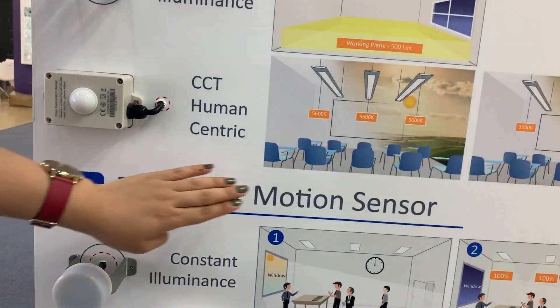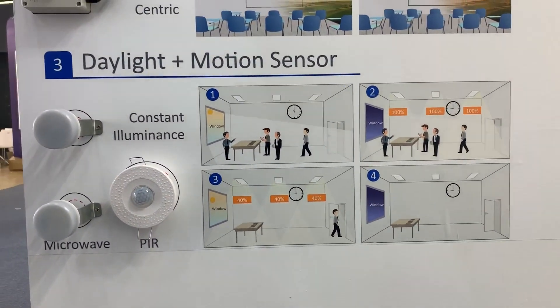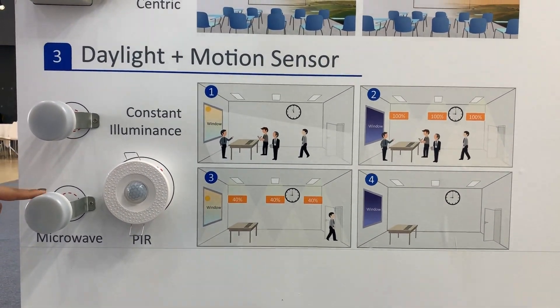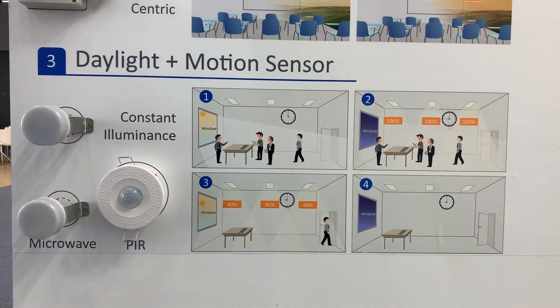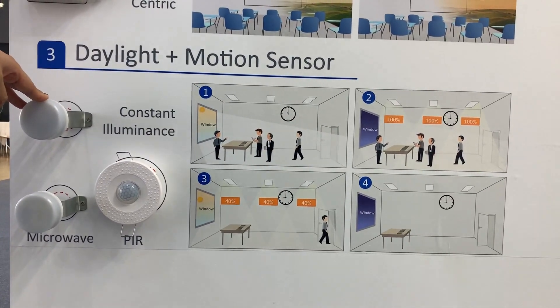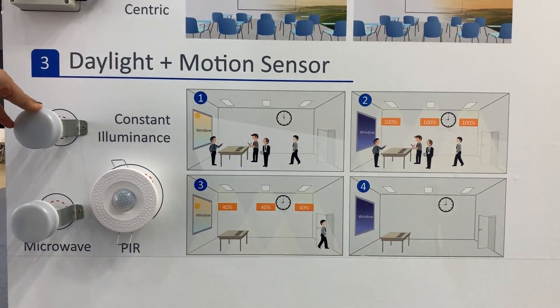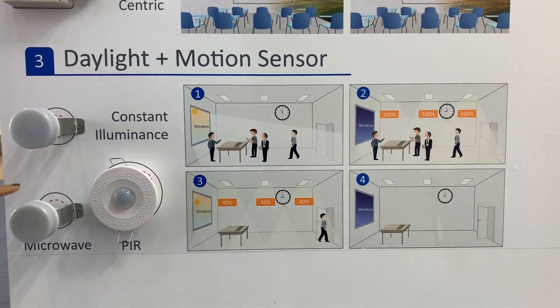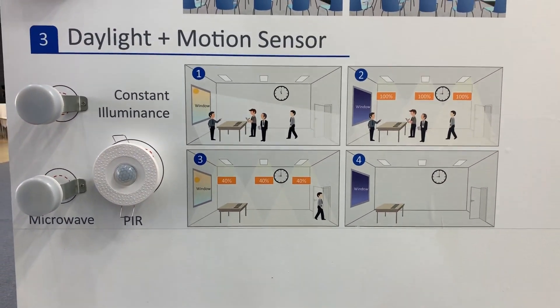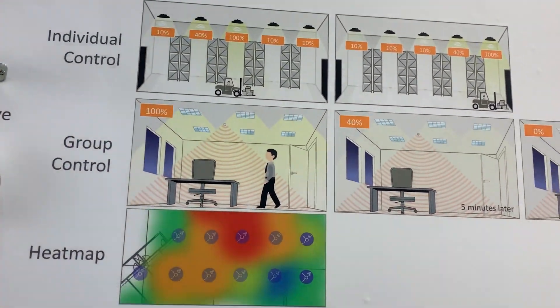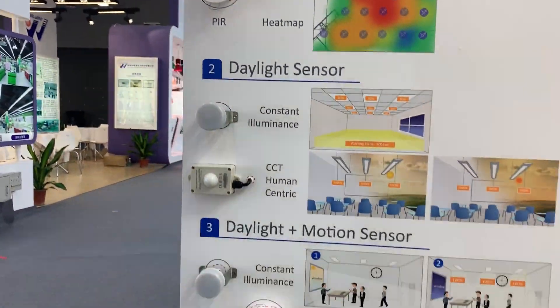The daylight sensor and motion sensor can also work together — combining a daylight sensor with a microwave motion sensor. When someone is present, the daylight sensor works to maintain a constant lux level, such as 500 lux. When nobody is present, the microwave sensor takes over to keep the lights at the waiting level or background level. That covers the introduction of the sensors.